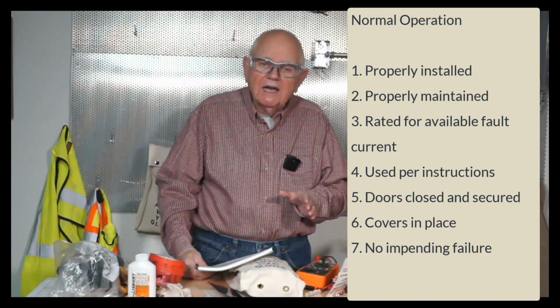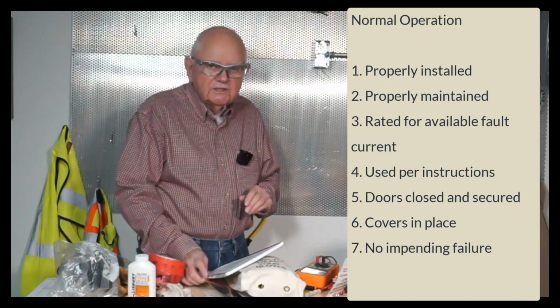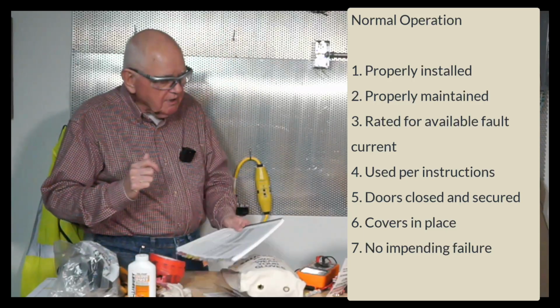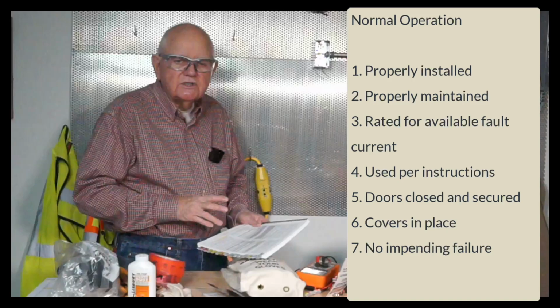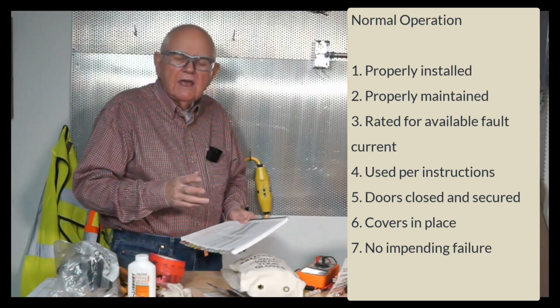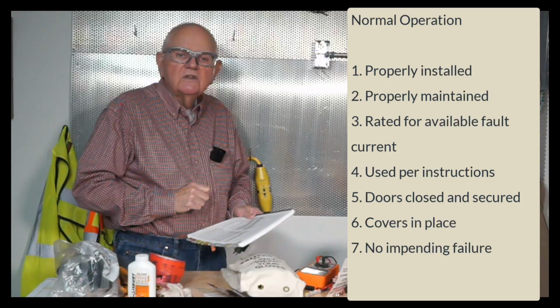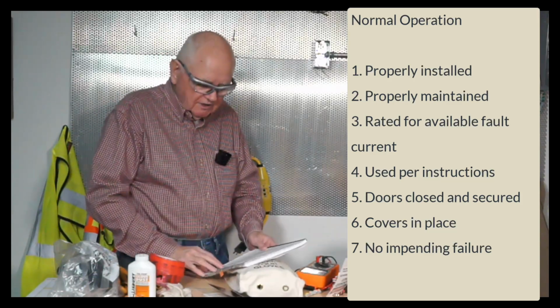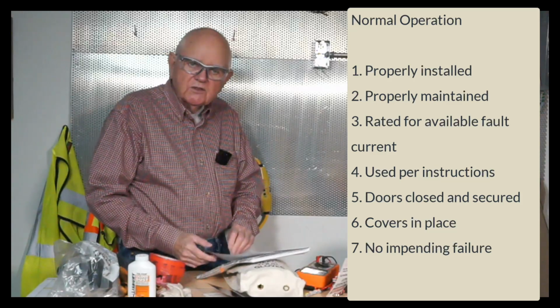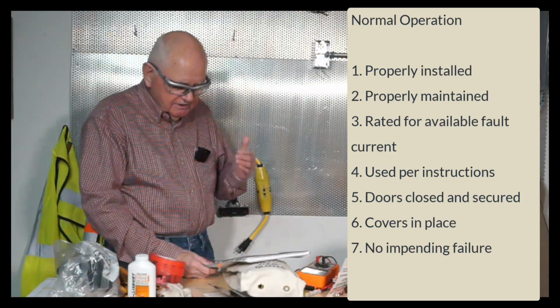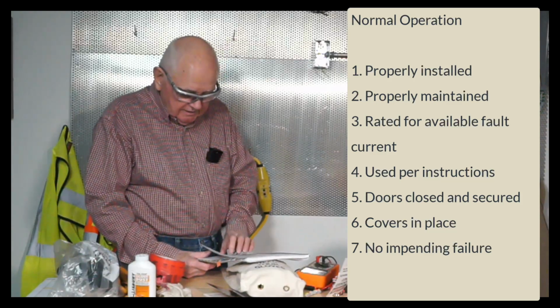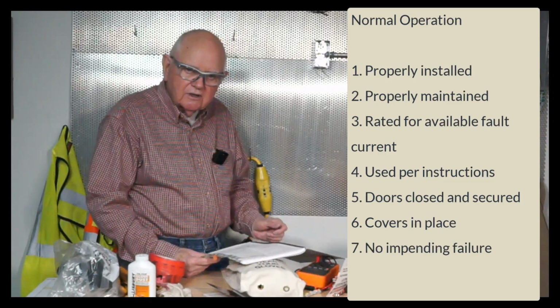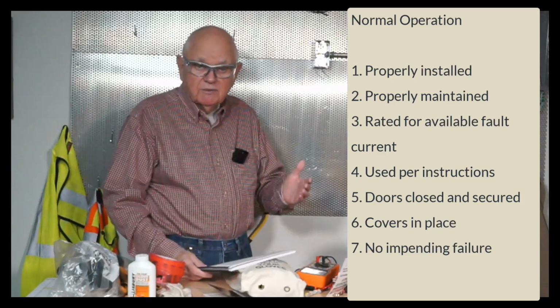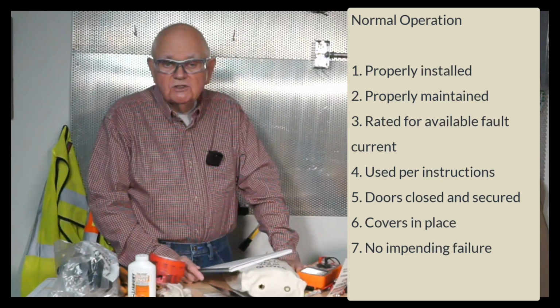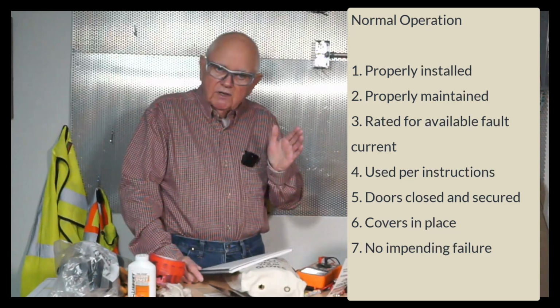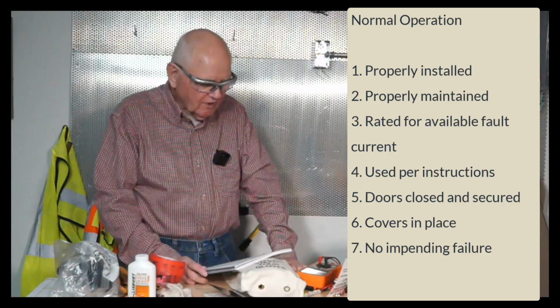So let's put those items up on the screen and take a look at them and talk about them just a little bit as a refresher. The equipment is properly installed and properly maintained. 2 separate items. So installed per the NEC requirements and then maintained per the requirements of NFPA 70B, the standard for electrical equipment. And whatever your maintenance program is, you follow that. You make sure the equipment's good, safe, installed properly, maintained properly. The equipment is rated for the available fault current. You can find that information on the nameplate, typically, or some type of nameplate data. But you want to make sure, manufacturer's instructions, whatever, in the event of a fault, we want to make sure the equipment's rated to handle that fault current.